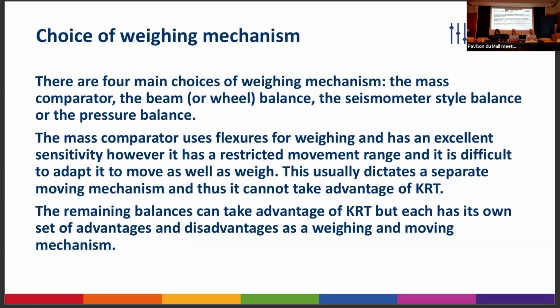Your choice of weighing mechanism is important. Many people use mass comparators, which are brilliantly good devices, but for this sort of work they normally have a restricted movement range, and so you can't adapt them easily to move as well as weigh over a long distance. So often you find that a balance with a mass comparator has a separate moving mechanism, and therefore you can't take advantage of KRT. All the other forms of balance can, but they all have their own advantages and disadvantages.